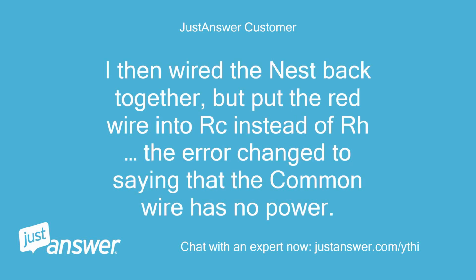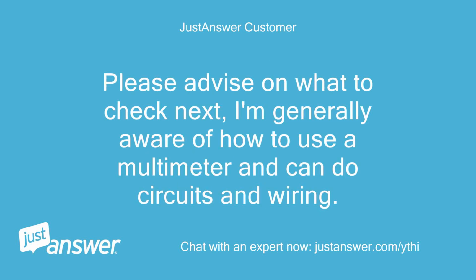I then wired the Nest back together, but put the red wire into RC instead of RH. The error changed to saying that the common wire has no power. Please advise on what to check next. I'm generally aware of how to use a multimeter and can do circuits and wiring.